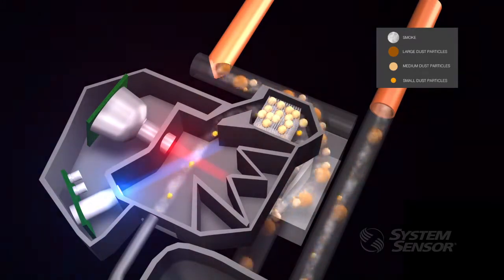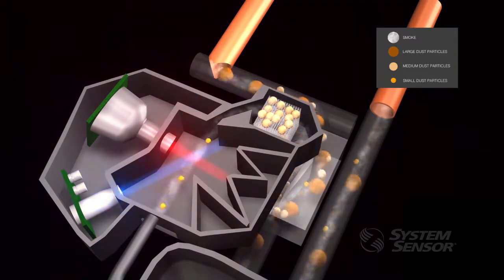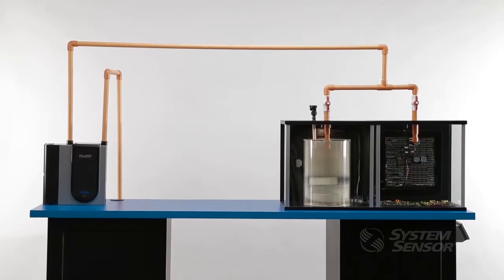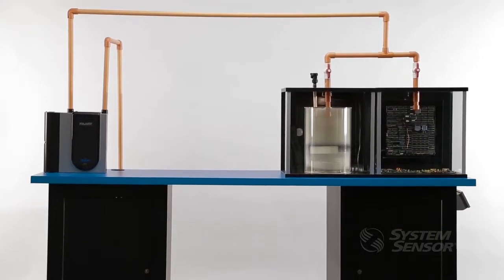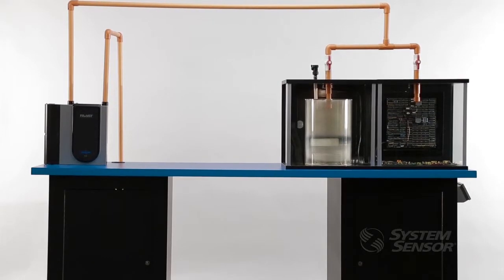and an infrared laser to identify and reject nuisance particulate. This demonstration will illustrate FAST's capabilities to detect smoke in the presence of high levels of dust by simulating a wire burn in a data center environment while simultaneously being subjected to high amounts of dust.